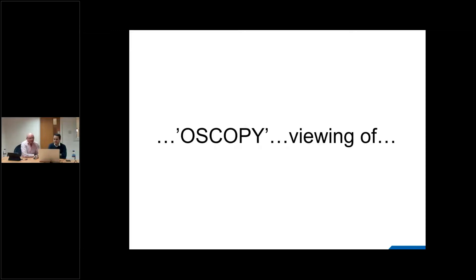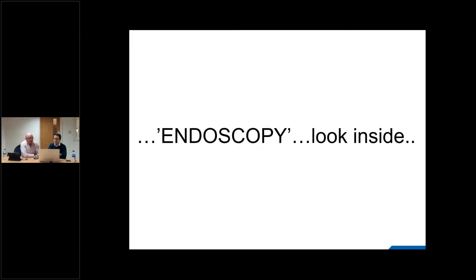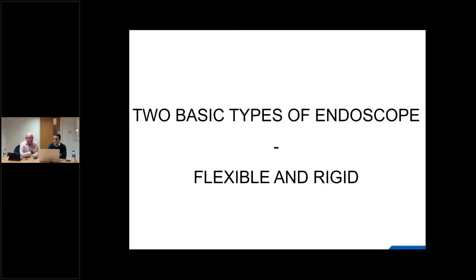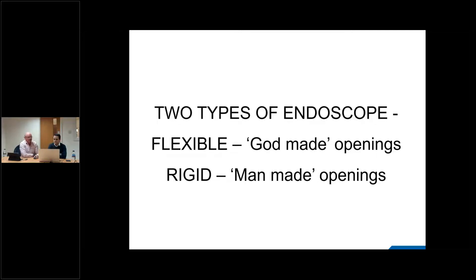Endoscopy means to look inside. There are basically two types of endoscope: a flexible endoscope and a rigid endoscope. Generally, flexible instruments go into natural orifices and rigid instruments go into man-made holes. Natural orifices are not uniform — there are lots of curves and bends — and clearly from a patient comfort perspective, putting a flexible endoscope into an opening with lots of bends and curves is much better.